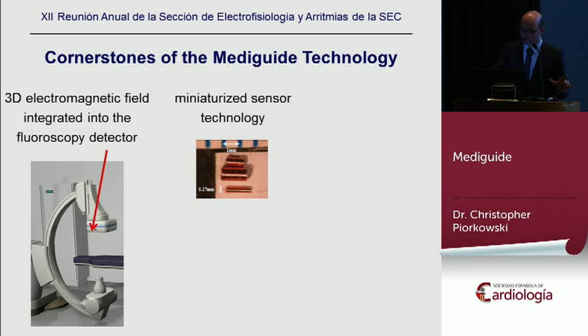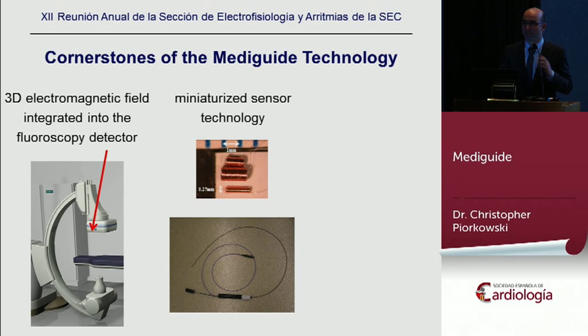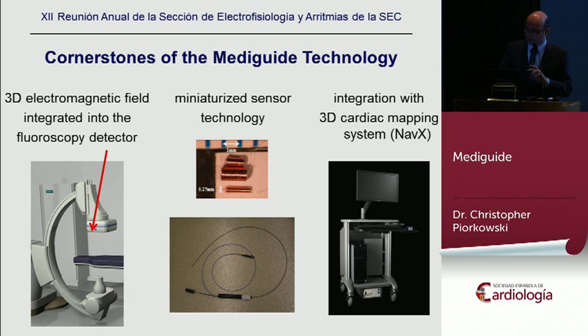As a further unique feature, this electromagnetic field has been married with conventional fluoroscopy in a sense that the field generators are built into the detector of a conventional X-ray system. By this pre-alignment, we have achieved auto-registration of the three-dimensional electromagnetic tracking space and the fluoroscopic imaging space by hardware setup. In fact, the system has to be slowed down to fit into the fluoroscopy because fluoroscopy typically has a time resolution of only 80 milliseconds. Later on, the technology has also been aligned with existing 3D mapping systems such as the NavX system. That means the three-dimensional coordinates are equal to each other.